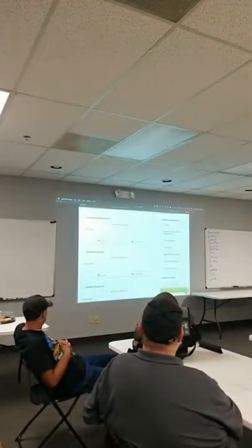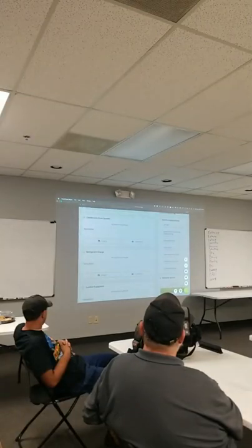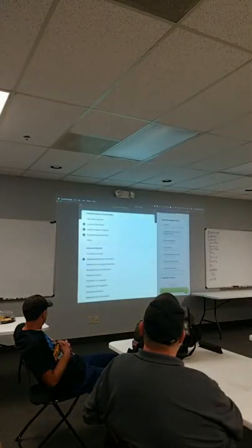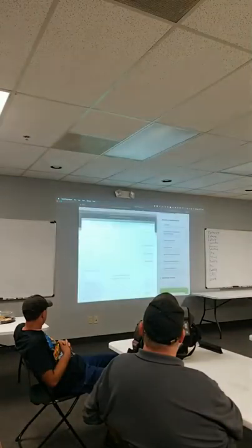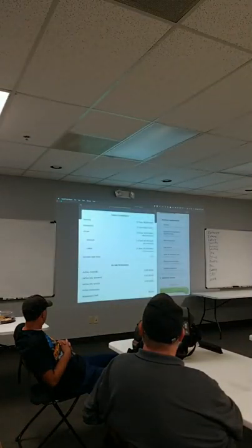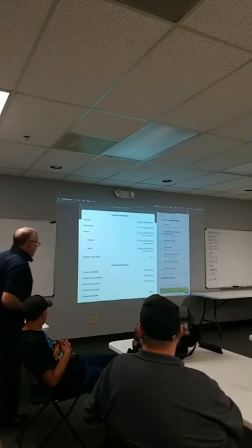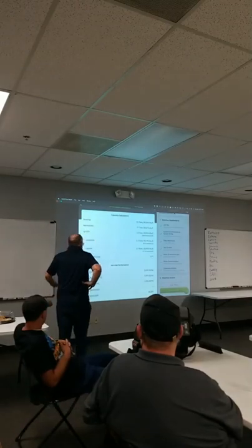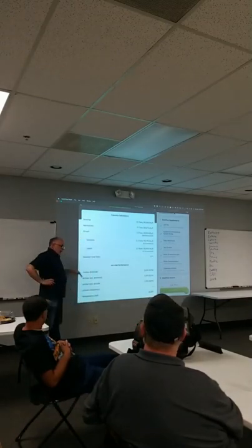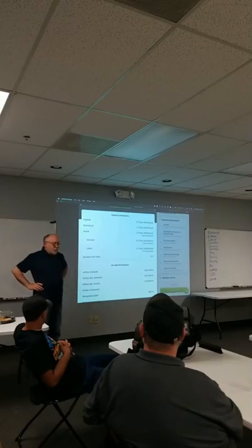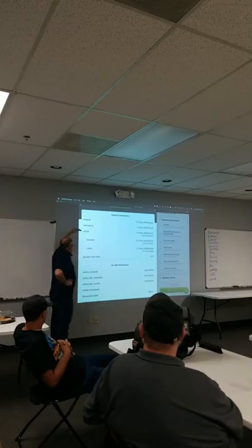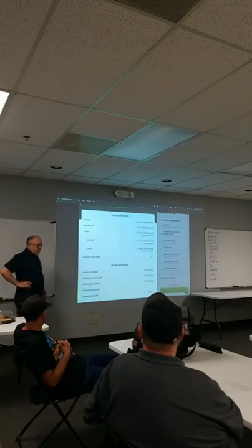And this hotkey, when you click on it, pulls up quick access to your corrective actions. It pulls up the performance of your system, if you want to look at your capacities or efficiencies. So in this case here, we can look at our sensible. Now this is an interesting one here, because when you're looking at performance, can somebody tell me why the sensible capacity is the most important number when it comes to performance? This I will tell you for a fact is a liar for how the equipment's really operating. That could be at 75%, be totally fine.